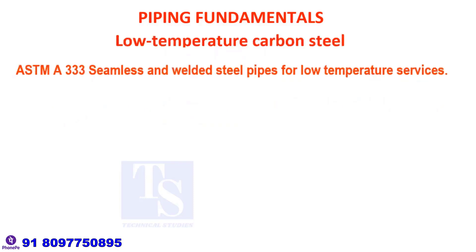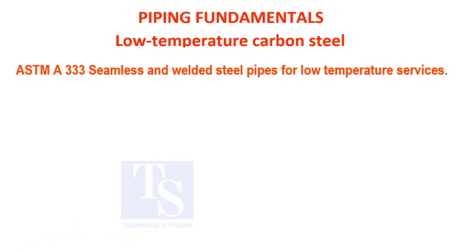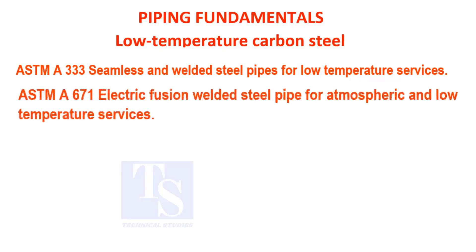Low temperature carbon steel: ASTM A-333, seamless and welded steel pipe for low temperature services. ASTM A-671, electric fusion welded steel pipe for atmospheric and low temperature services. Available sizes are larger than 16 inches.